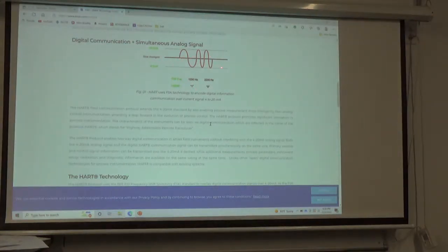This right here is going to an analog card or something else. But the card is looking for the analog signal. Does the card see this? No. The cycle is too fast. The card is not fast enough to catch all that. So it's just catching the average of that signal. Remember, the wall outlet is 60 hertz. This is 1200 and 2200 hertz.